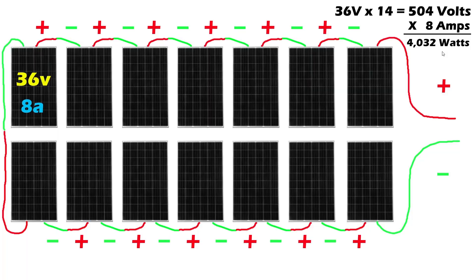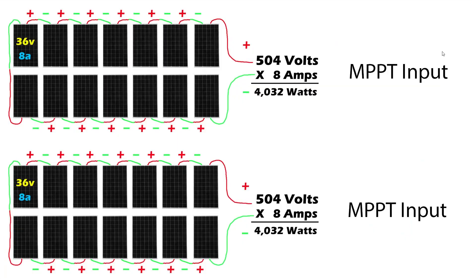When I'm done I'll have two strings of 14 panels each. The positive and negatives left over connect into the MPPT inputs. My inverter has two separate inputs and it's very important to know the voltage ranges on each. In my case they are both up to 550 volts, so we won't end up with 1,008 volts — we'll end up with 504 volts per MPPT input.